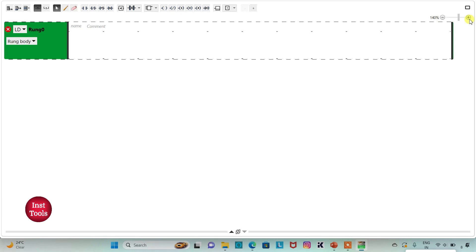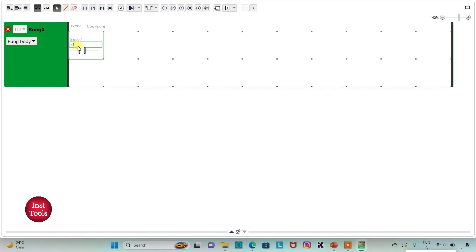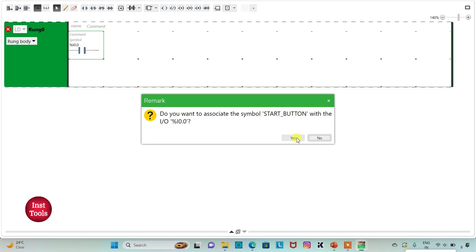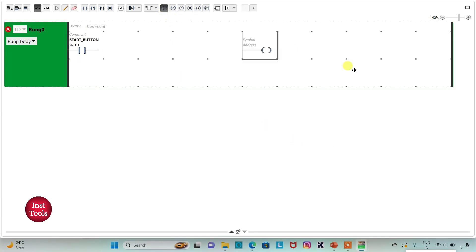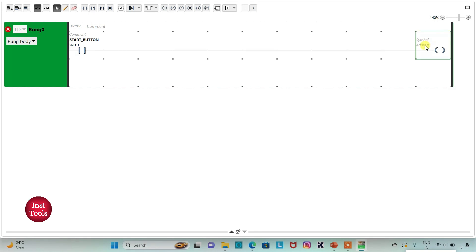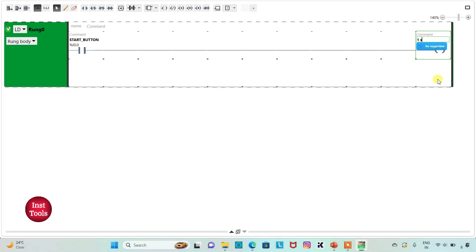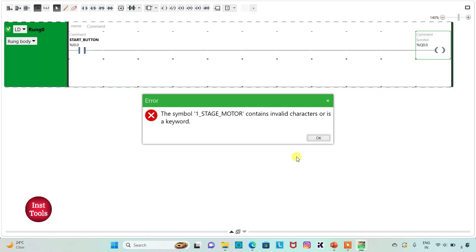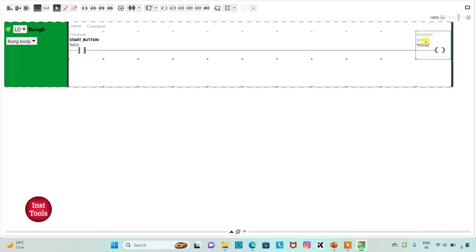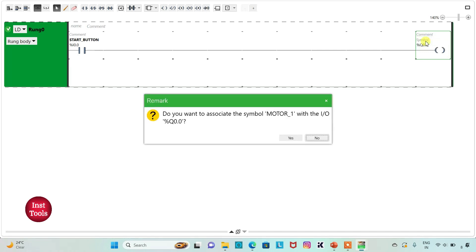I can also click on this option for full screen mode and then zoom in. Firstly, I will insert a normally open contact for the start button and assign address I0.0 to it, adding the symbol 'start button'. Then I will insert a coil and assign address Q0.0 to it, adding the symbol 'motor 1' for the first stage motor.